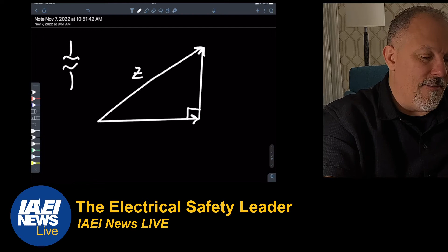Think about a transformer. Let's say you had 500 kVA and 4% Z. Both of those numbers can find themselves on the power triangle. Let's look at the impedance, Z — that percent Z value is right there. Z is comprised of a resistance, R, and a reactance X. What we call this up here, because it's on that axis, we call J.